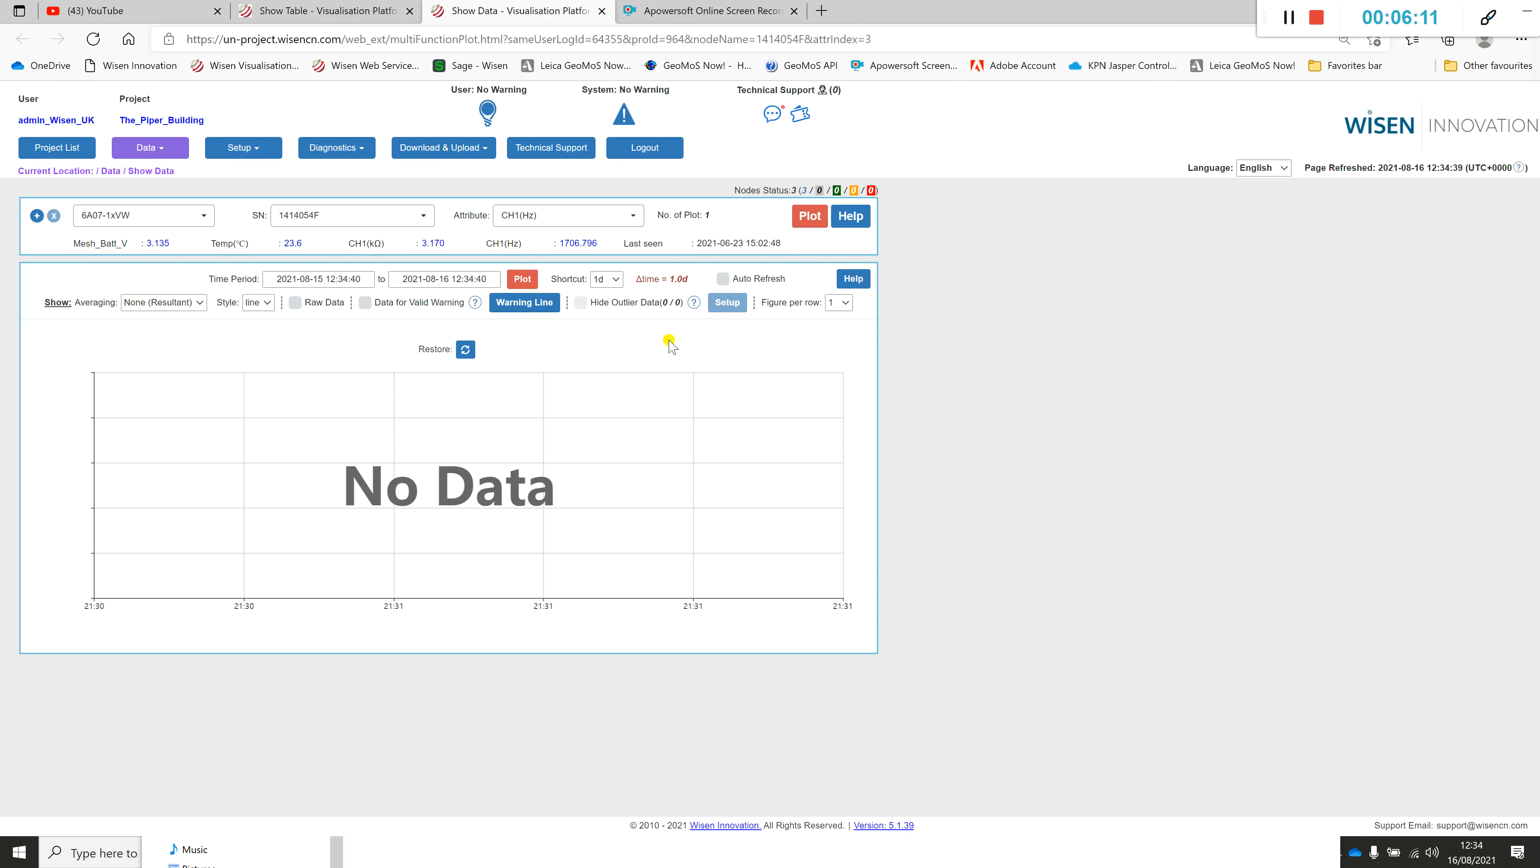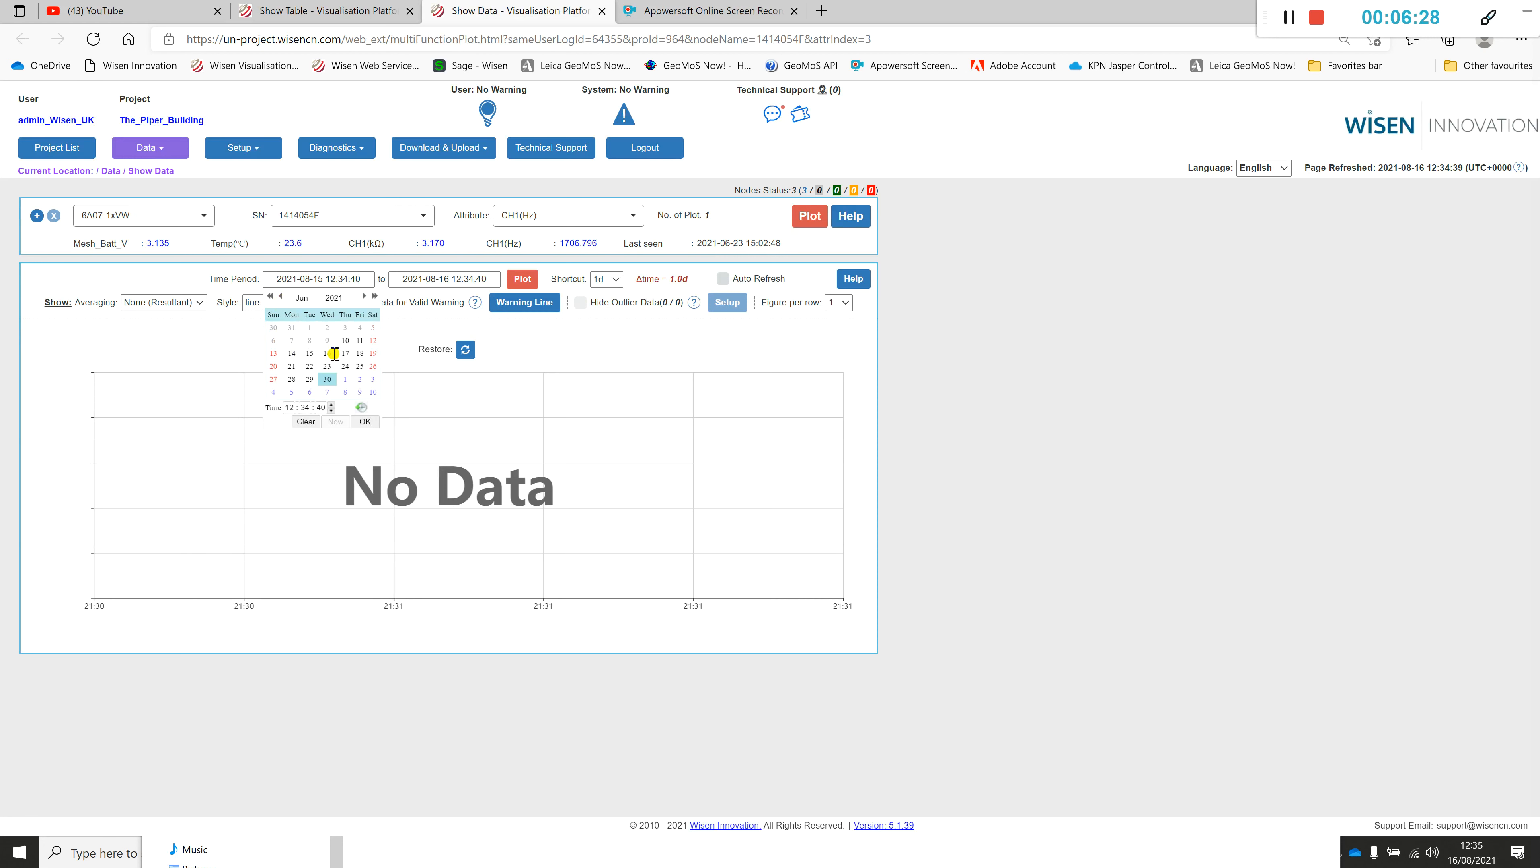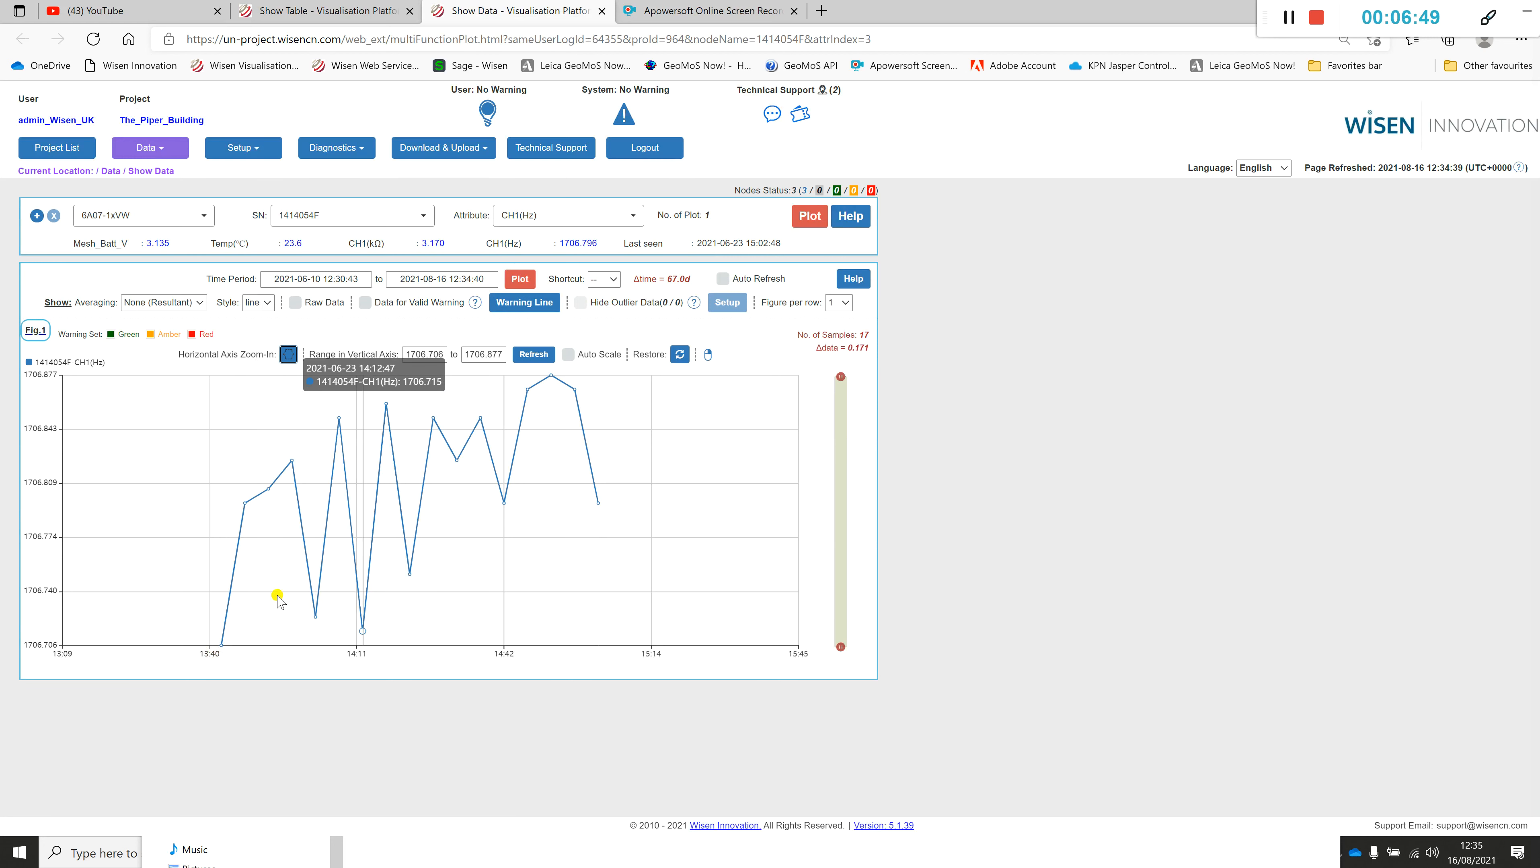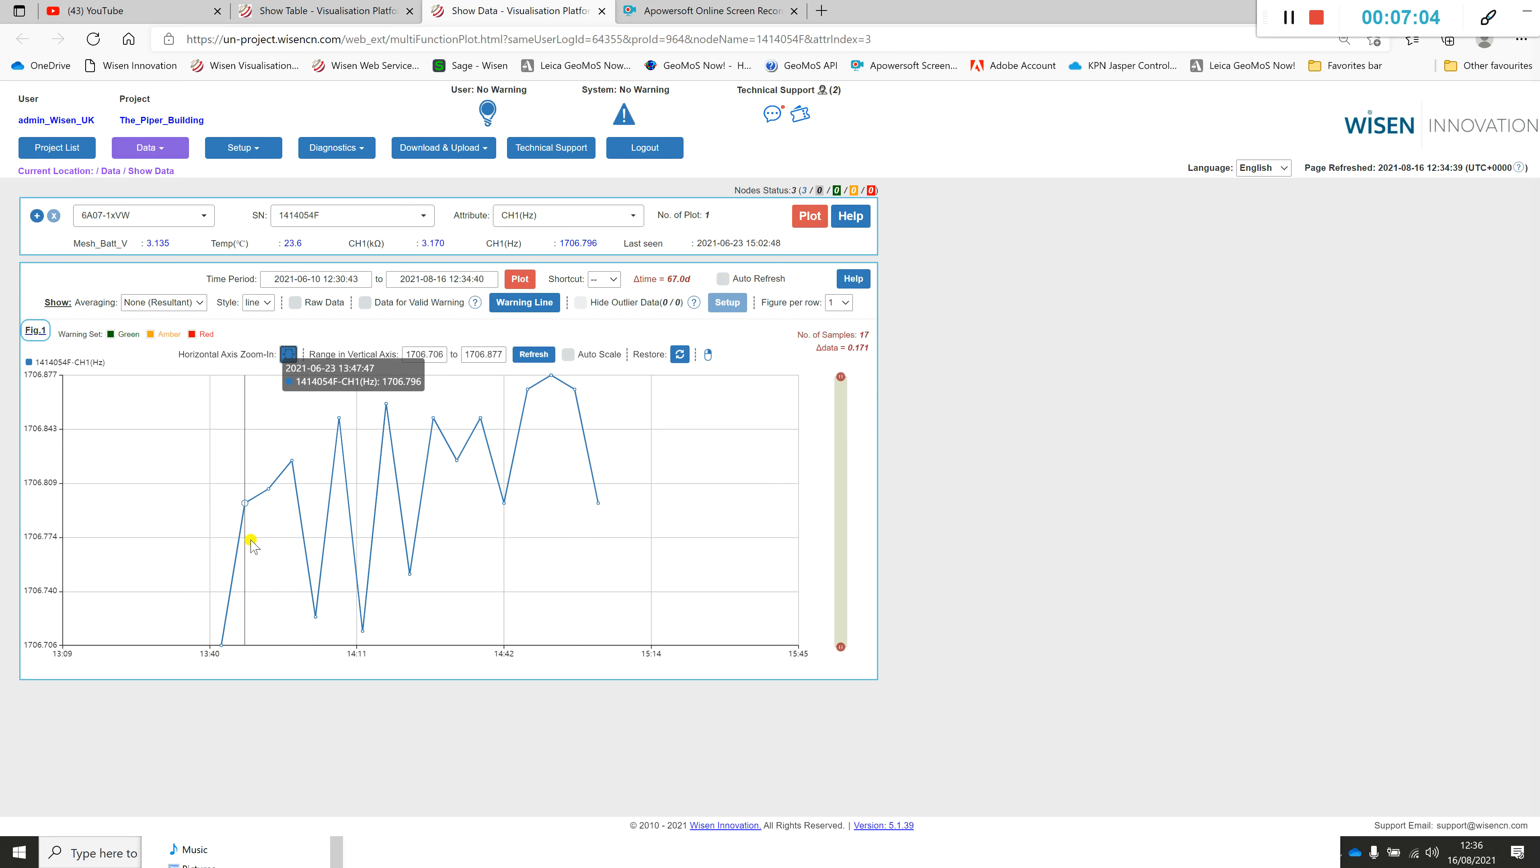We review this graphically. We can see here the time and the date that this was installed. Initially you would have that initial value. It's important that you're selecting this value based upon an average or a median or you're confident that this is an initial value, not potentially installed in a site office before your final installation. Make a note of the actual hertz value itself.